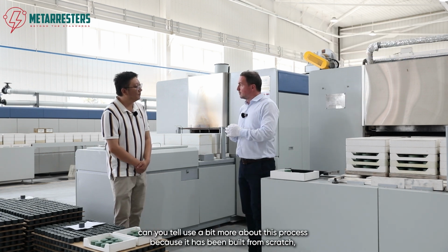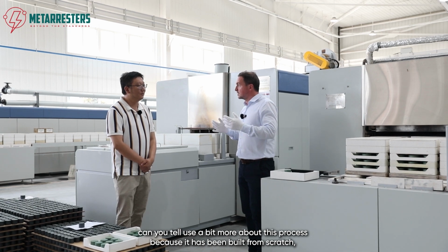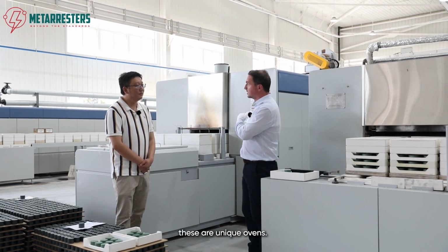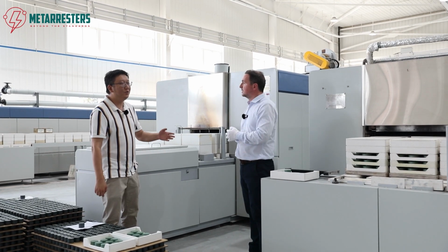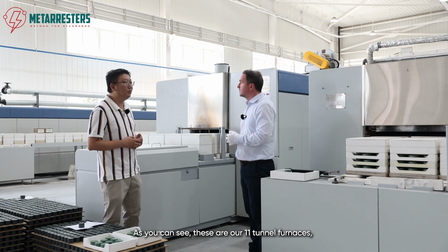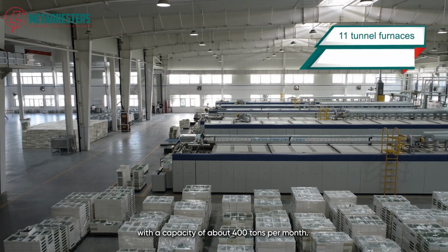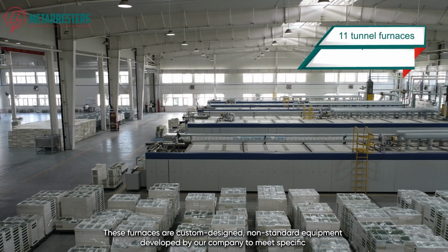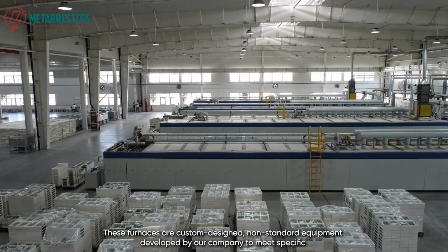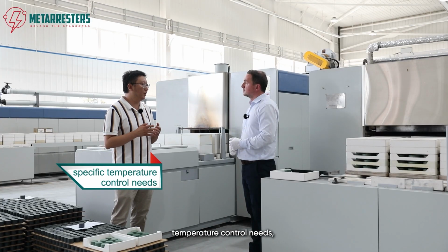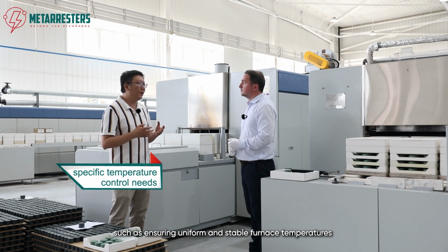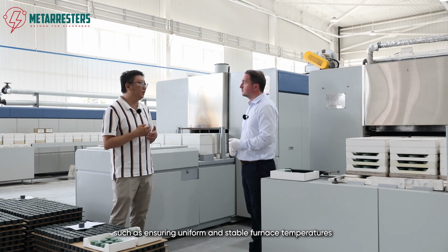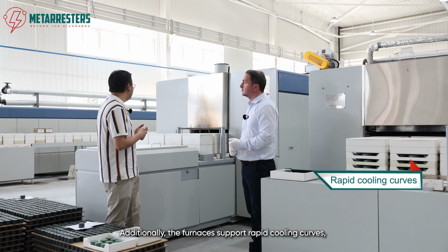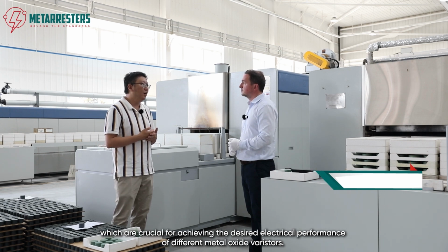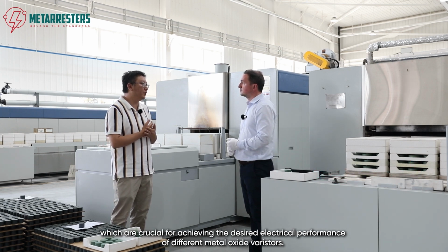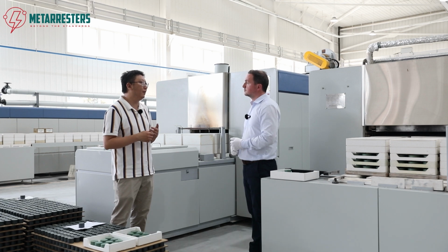Can you tell us a bit more about this process? Because it has been built from scratch, though these are unique ovens. As you can see, these are our 11 tunnel furnaces with a capacity of about 400 tons per month. These furnaces are custom-designed, non-standard equipment developed by our company to meet specific temperature control needs, such as ensuring uniform and stable furnace temperatures. Additionally, the furnaces support rapid cooling curves, which are crucial for achieving the desired electrical performance of different metal oxide varistors.